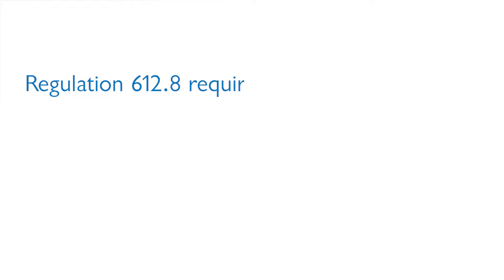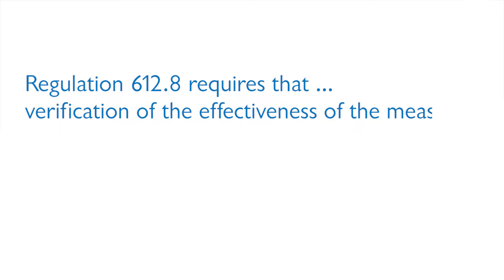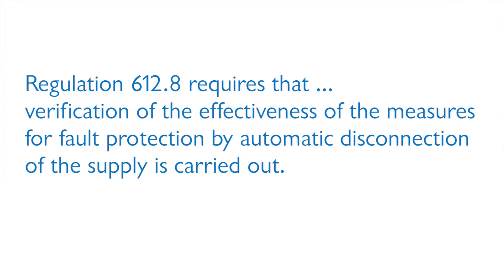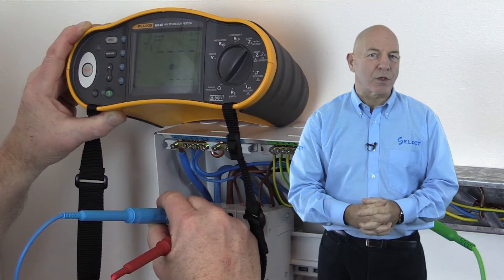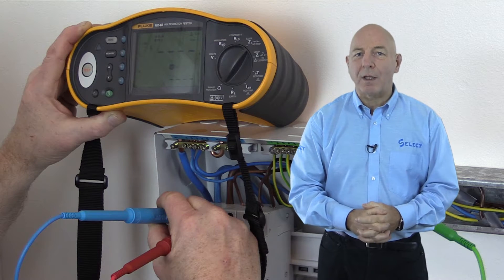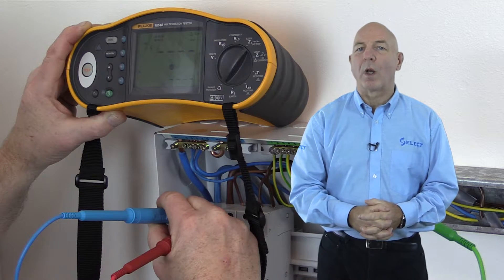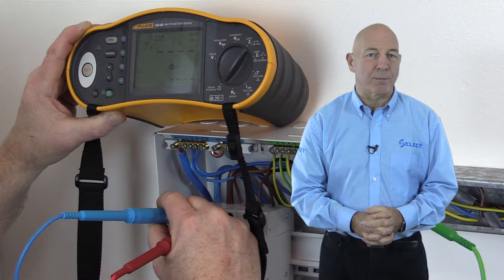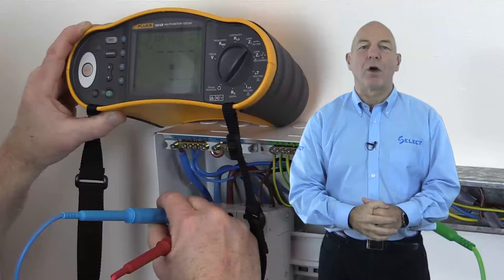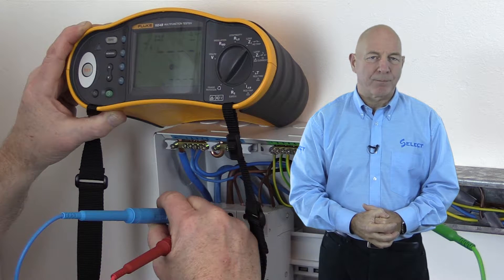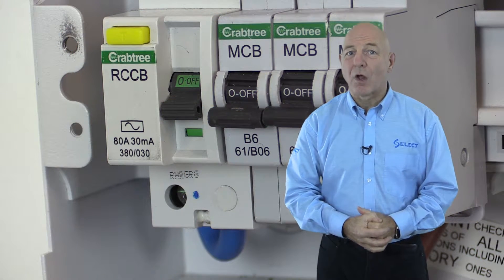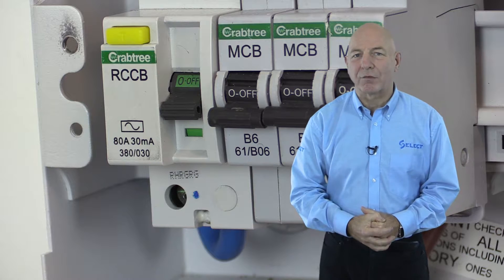Regulation 612.8 requires that verification of the effectiveness of the measures for fault protection by automatic disconnection of the supply is carried out. Regulation 612.8.1 requires that compliance with regulation 411.4 shall be verified for TN earthing systems by, firstly, measurement of the earth fault loop impedance, and secondly, verification of the characteristics and/or effectiveness of the associated protective device.